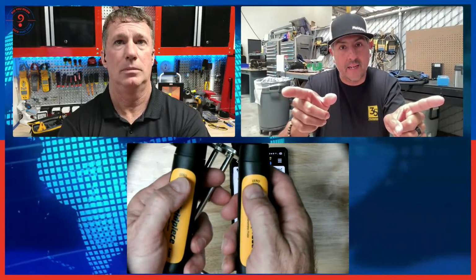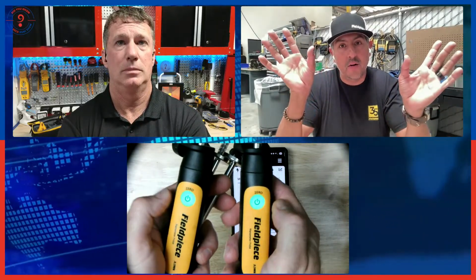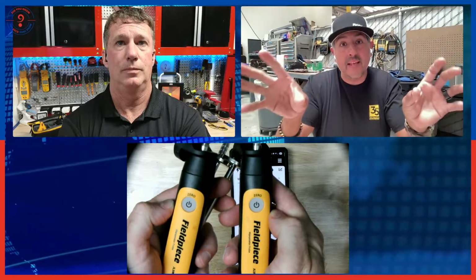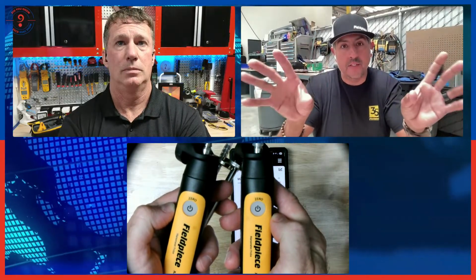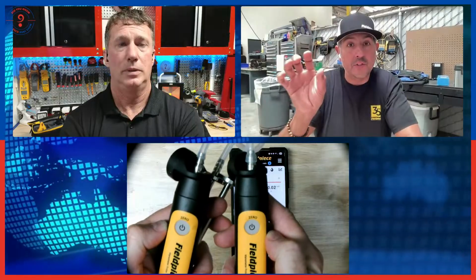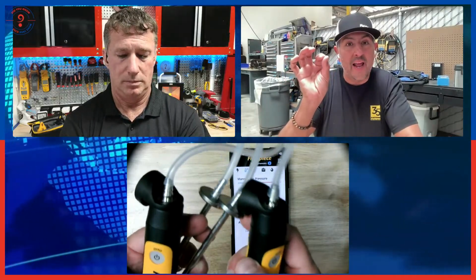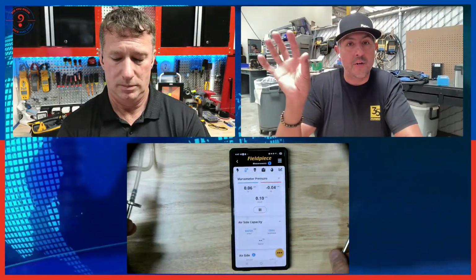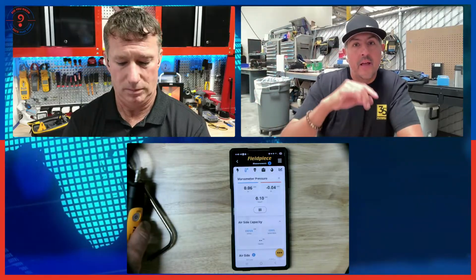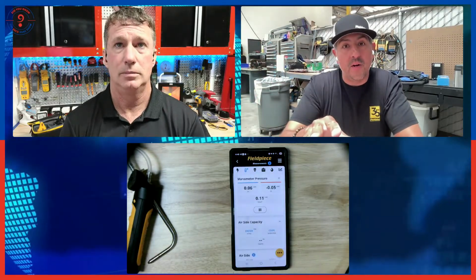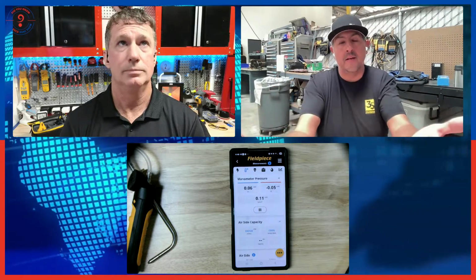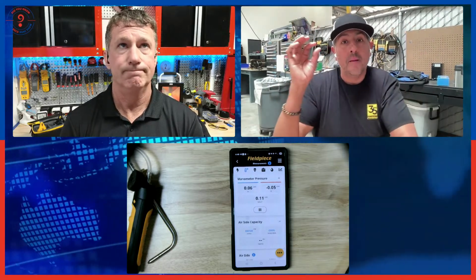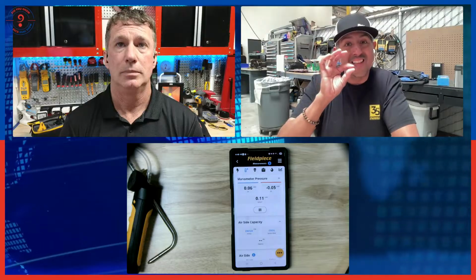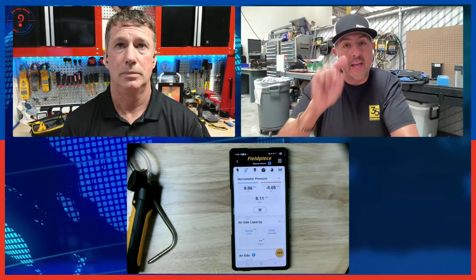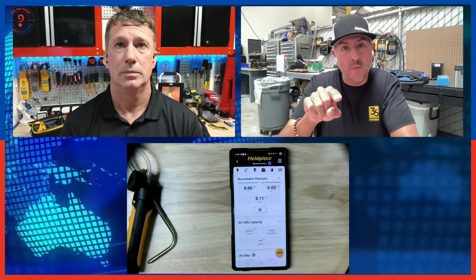And so first you would power those on. You hold them for about a second until you see green, then you let go. And if they're blinking, that means you are in normal operation mode and we're ready to sync. If you held it too long, you're going to get a solid green, and that means you're in data logging mode, and you don't want to do that, so turn it off and try it again. Okay. And so it looks like you've already previously synced those manometers because the measurements instantly came up. But if you had not, it would say link tool there, and then you would tap on that. So you could tap on any one of those numbers on that screen for the manometers.